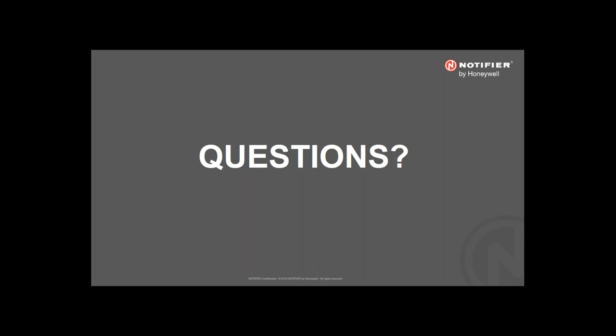Okay, wonderful, thank you. So we have time for one last question, and I want to thank everyone for sending in their questions. As I mentioned, we will follow up specifically if your question has not been answered. My last question, Jacob, is something you had just addressed a few minutes ago regarding ceiling mounting requirements for CO detectors. Could you just repeat that? Sure. Ceiling mounted detectors for CO, you can mount the detectors on the ceiling. They just need to be no less than 4 inches away from the wall and within 3 feet of the peak if it's a vaulted ceiling.